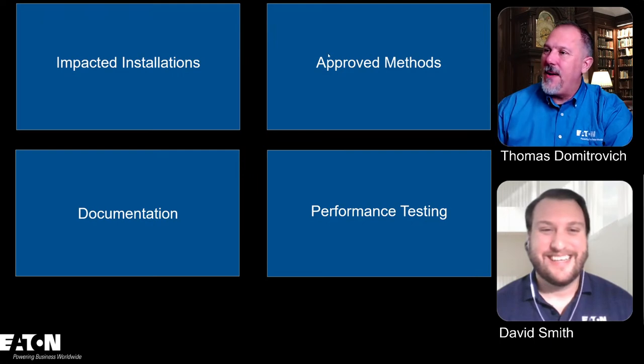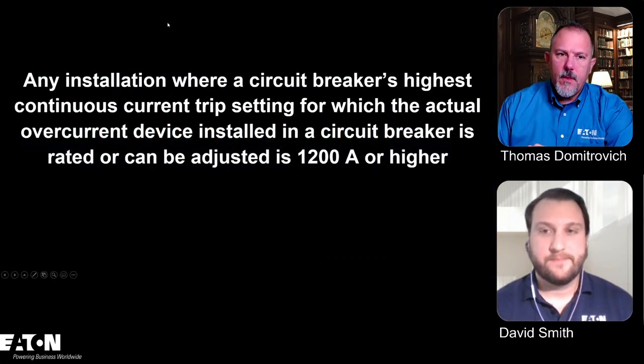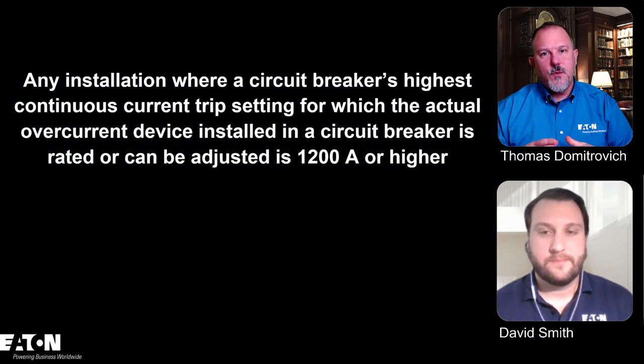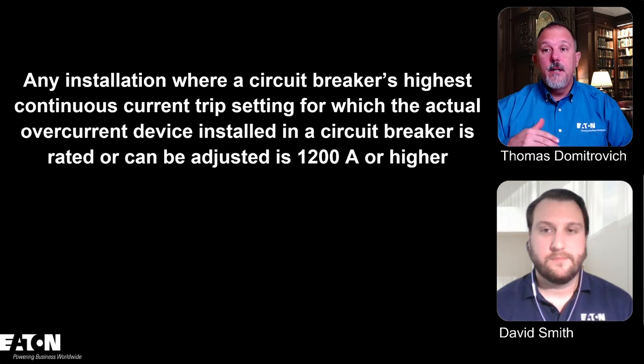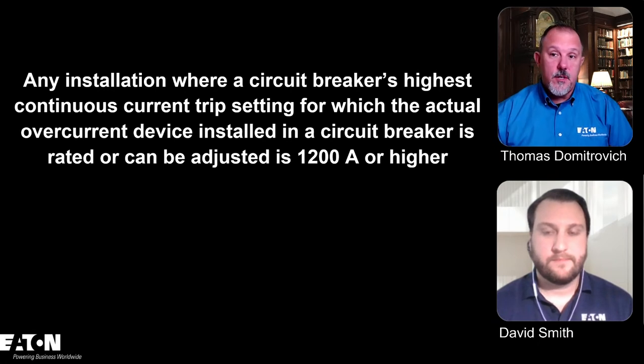What we were talking, impacted installations first? Yes. All right. So let's talk about the impacted installations. We're going to be looking at the parent text. So the parent text of that section of the code says any circuit breaker where the highest continuous current trip setting for which the actual overcurrent device installed in a circuit breaker is rated or can be adjusted is 1200 amps or higher.